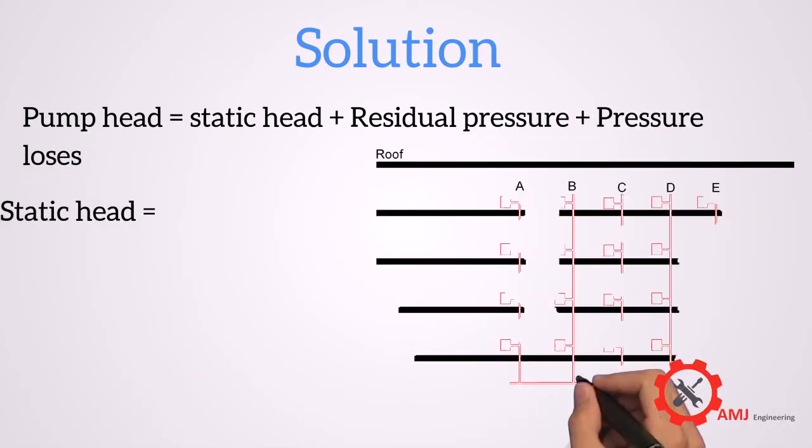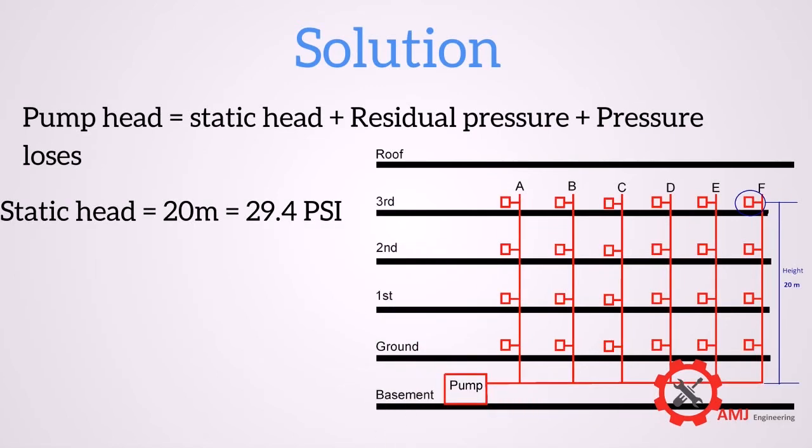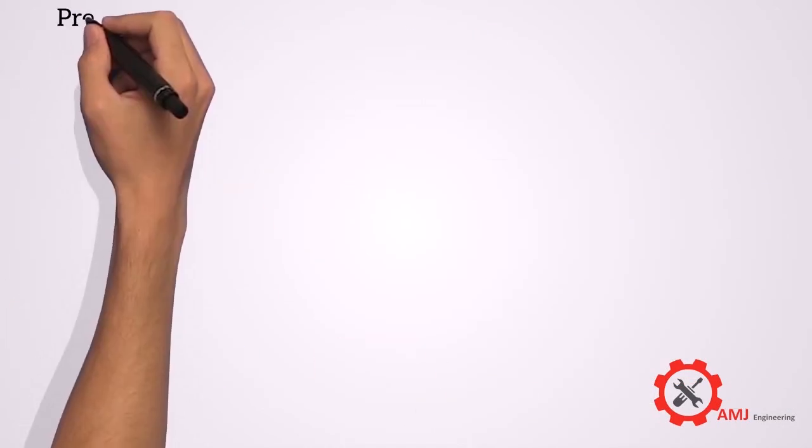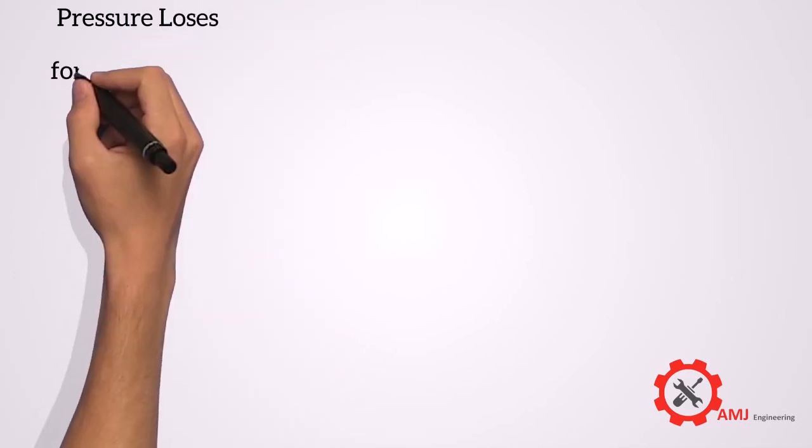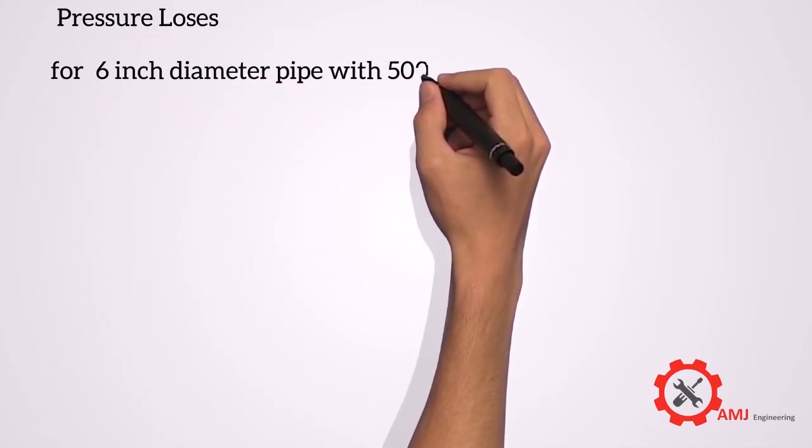Static head equals 20 meters equals 29.4 psi. Residual pressure equals 100 psi being class 1. Pressure losses for the six inch diameter pipe with 500 GPM.